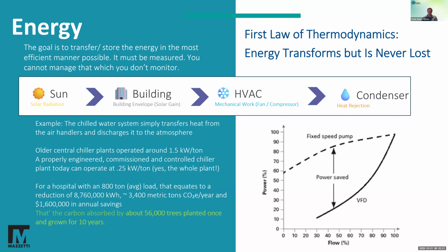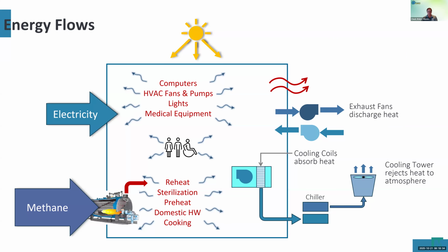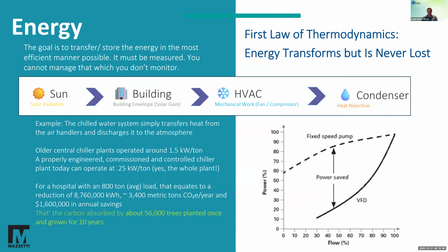It's a cubic relationship, and it's even more pronounced if you look at the affinity laws regarding the relationship between speed, pump, and power. But at 80% flow, for example, if you look up the curve, I'm at 50% energy. So the last 20% of flow takes 50% more power.